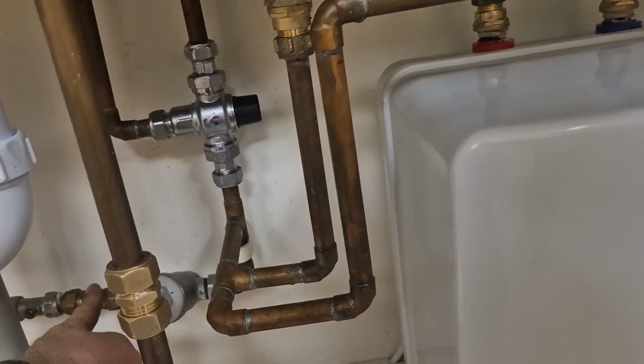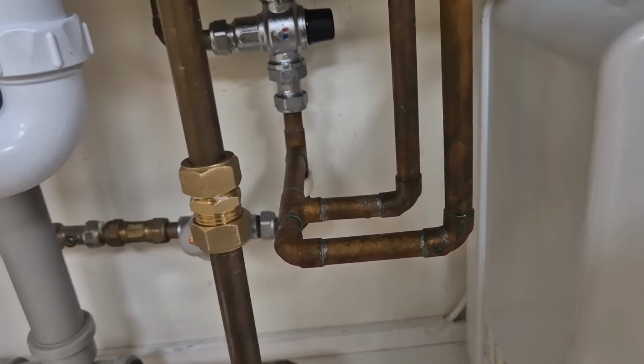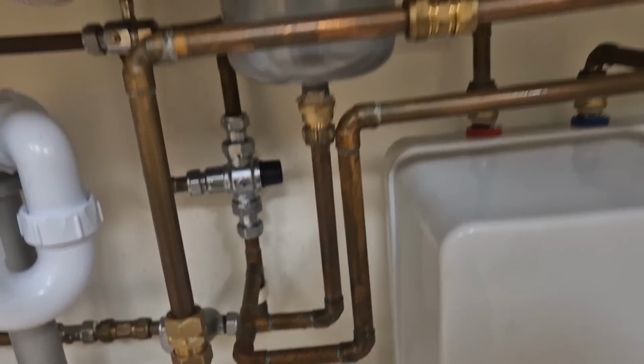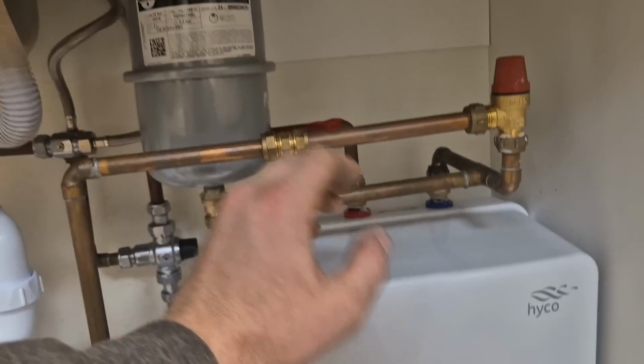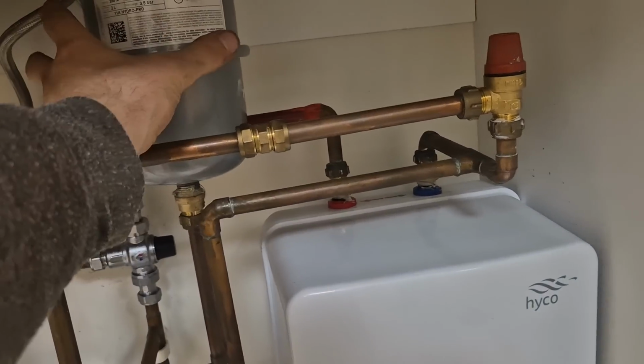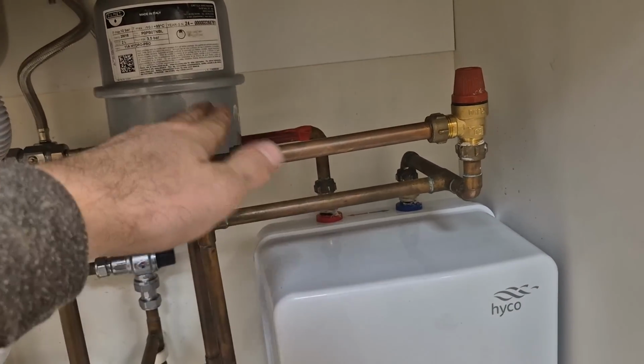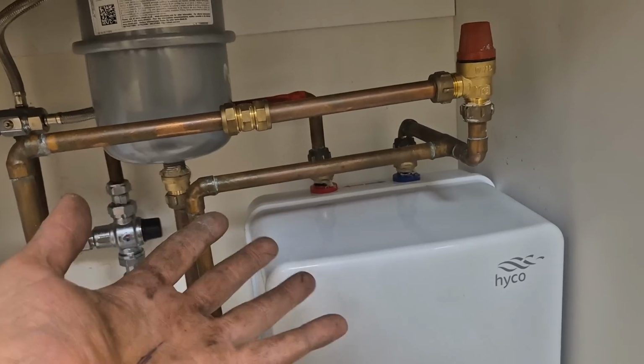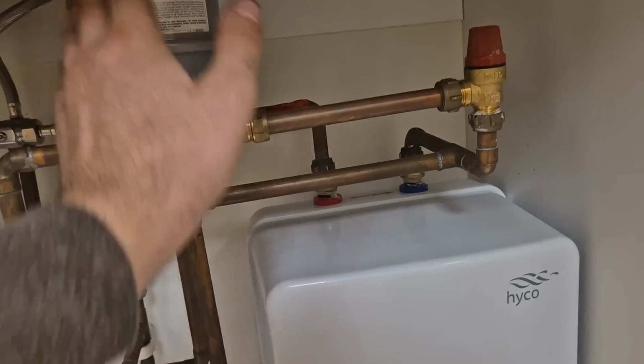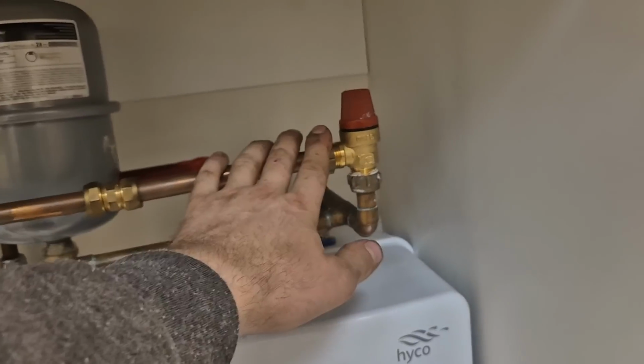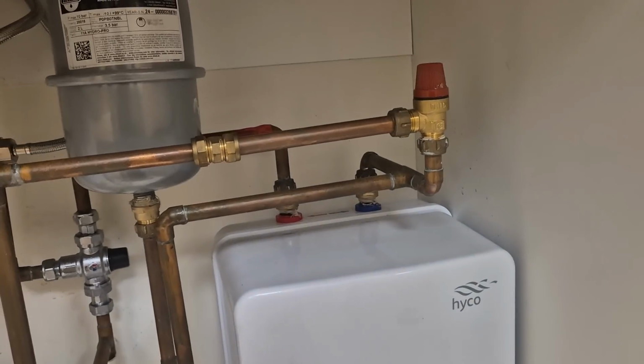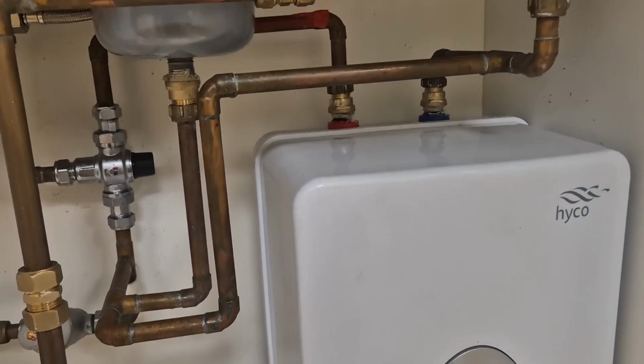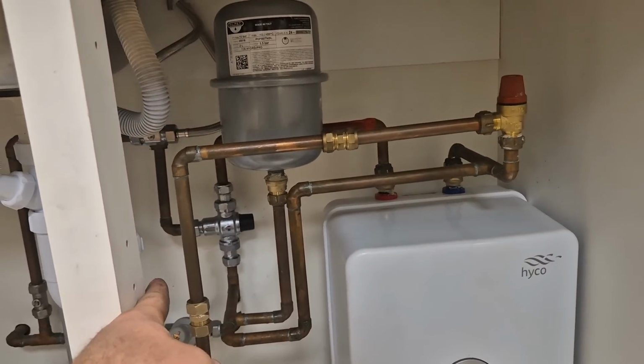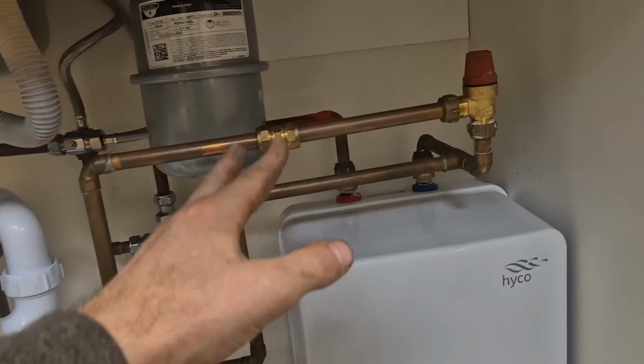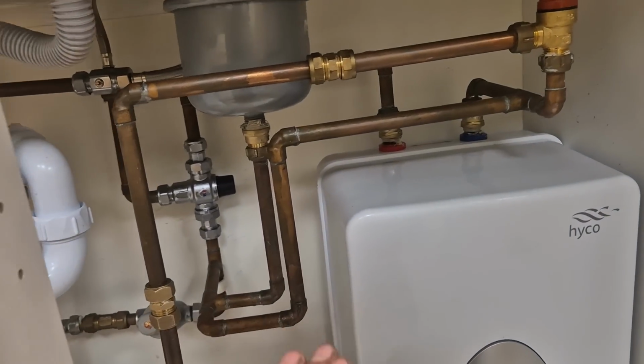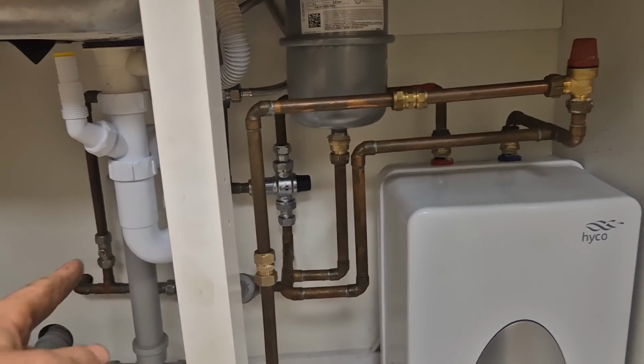If you've got enough pipework, I can't remember what it is, 1.6? You don't need to put a check valve and an expansion vessel on it. But what happens is, as the heater heats up, that takes up the volume of water, so obviously hot water rises. Hot water gets larger, so that takes up the expansion. If it can't take the expansion, it'll blow it out, in theory. That's what should happen. As I say, if you've got enough pipework, you don't need to put an expansion vessel and a non-return valve on it, because it can expand back into the main.